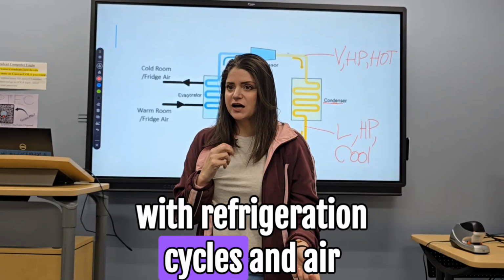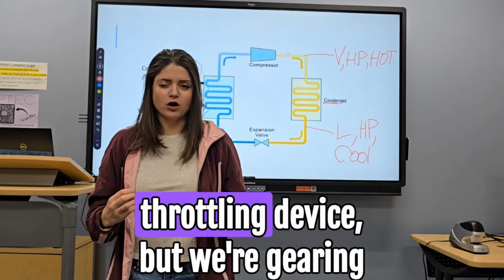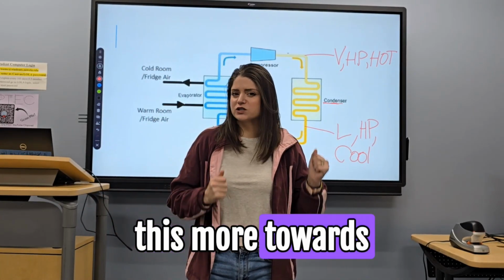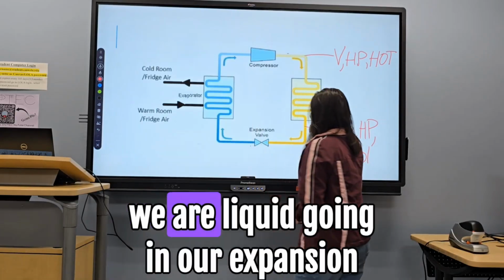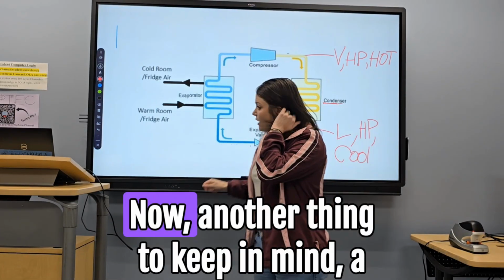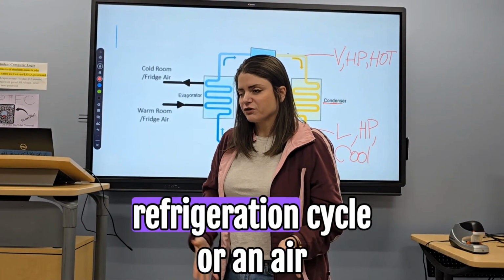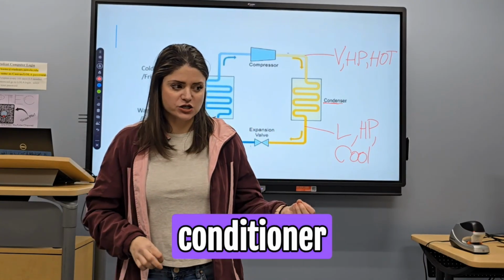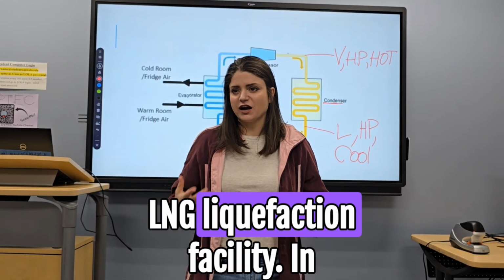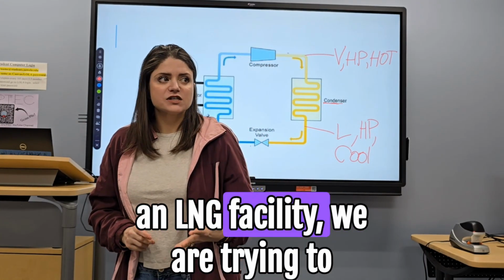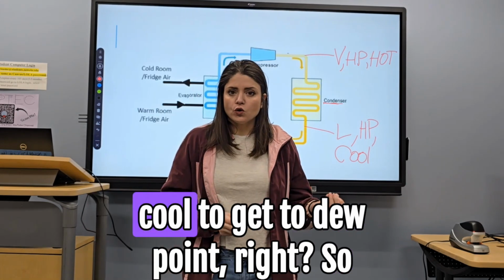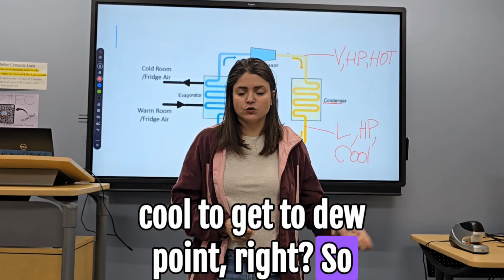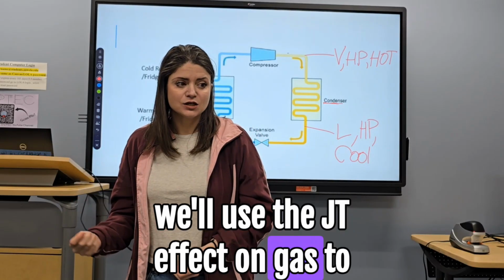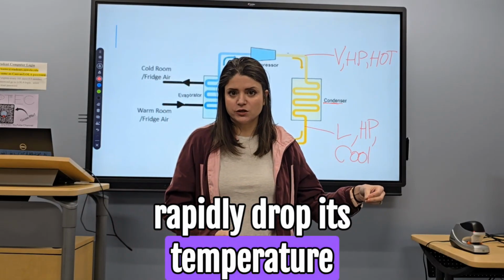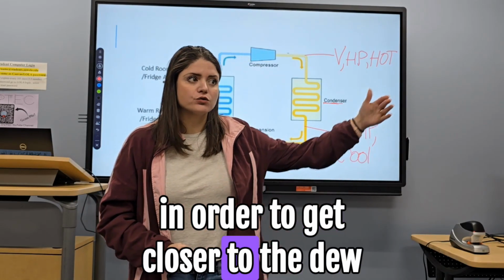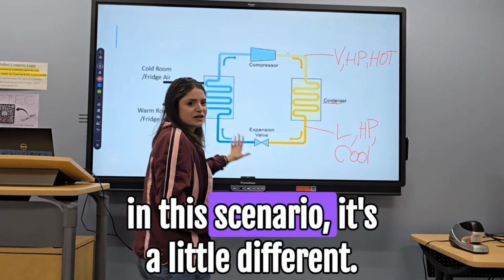With refrigeration cycles and air conditioners, they may call this the throttling device, but we're gearing this more towards LNG. So we are liquid going into our expansion valve. Now, another thing to keep in mind, a refrigeration cycle or an air conditioner cycle is not the same as an LNG liquefaction facility. In an LNG facility, we are trying to cool to get to dew point, right? So we'll use the JT effect on gas to rapidly drop its temperature in order to get closer to the dew point of LNG.